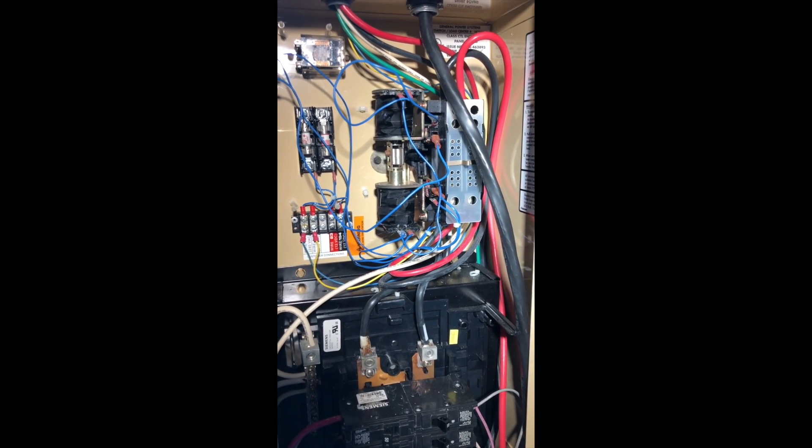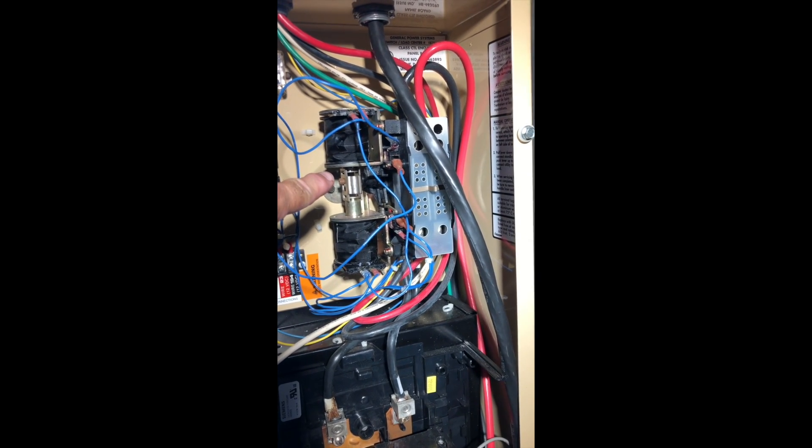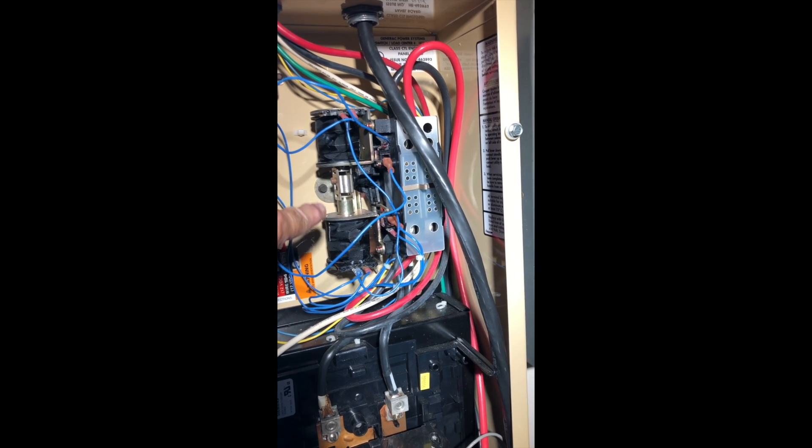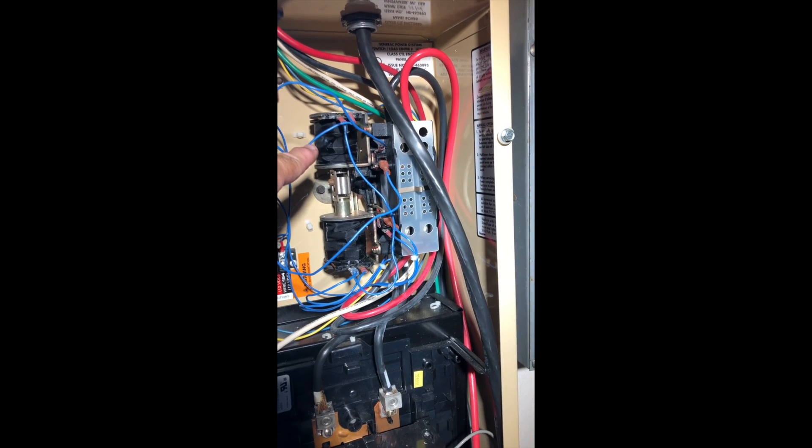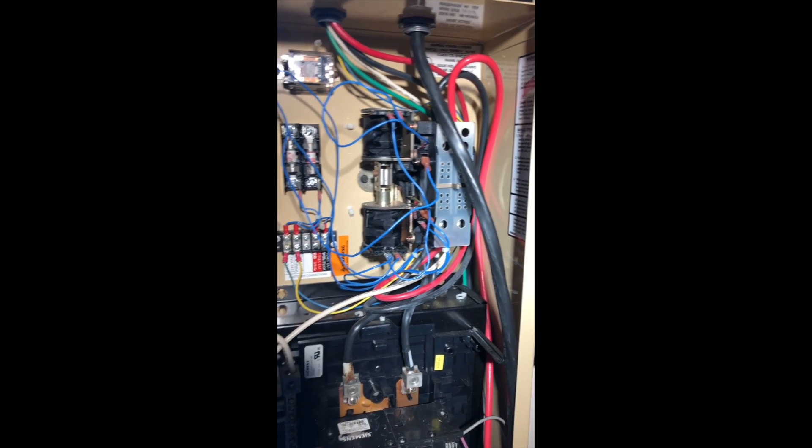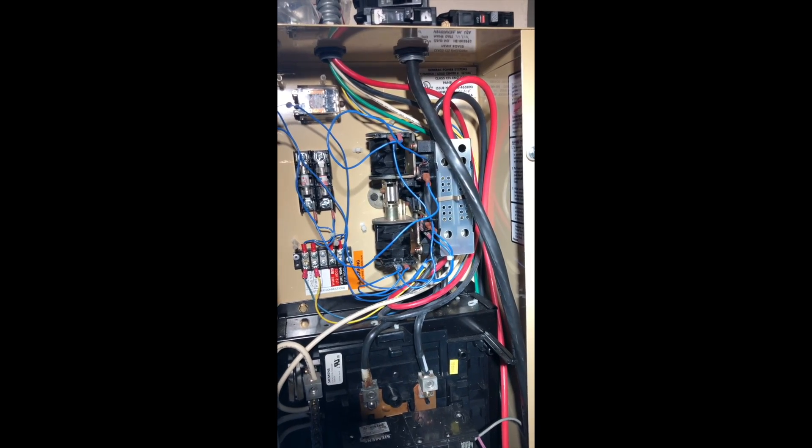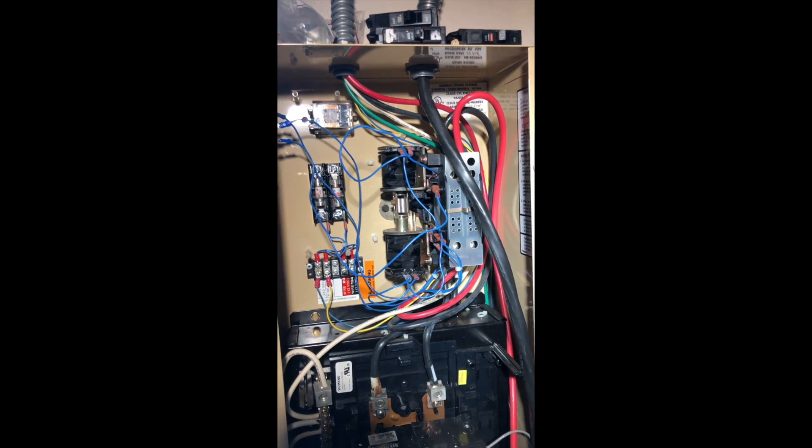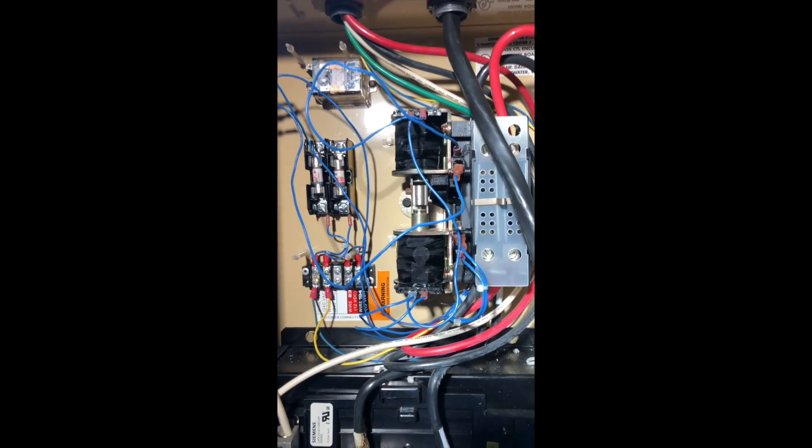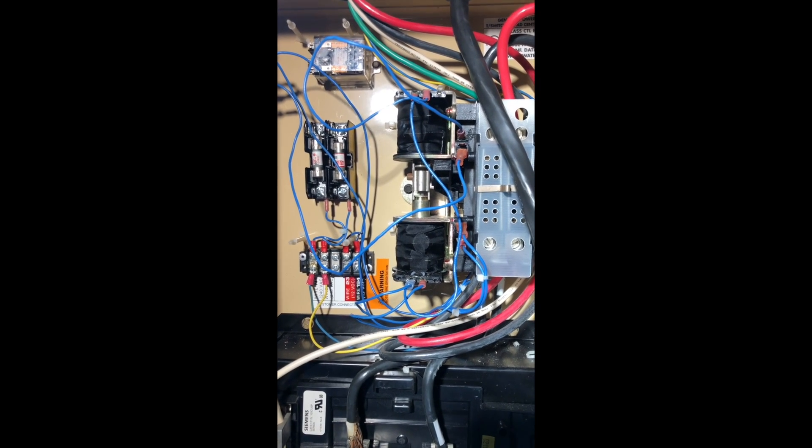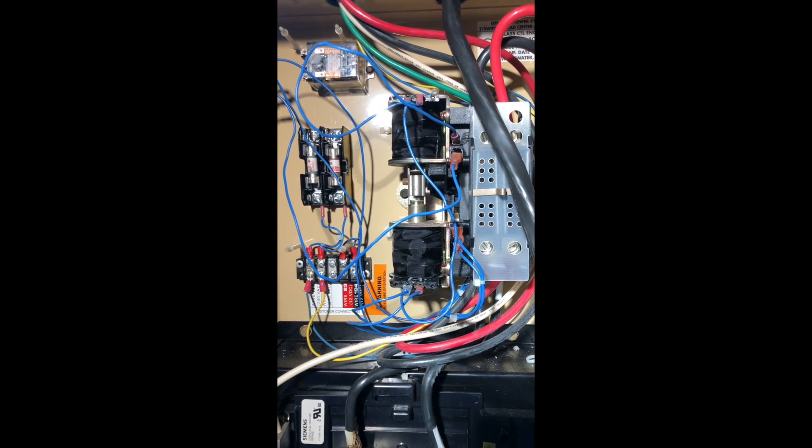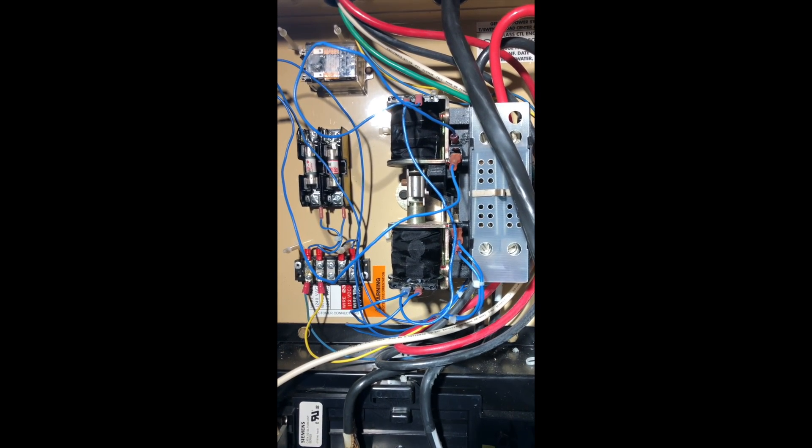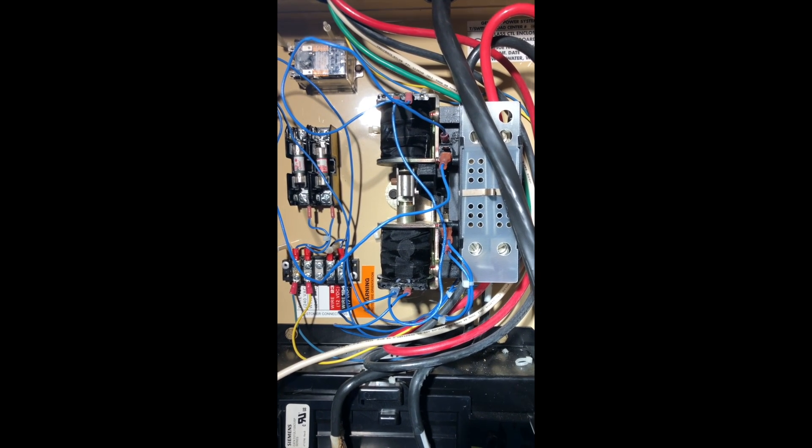I figured out how to - this is the transfer switch mechanism. Basically, it's two electromagnets, one on top of each other. They are AC powered, they're not 12 volt powered. There is a 12 volt component to this that has to do with the sensing unit that sends the commands to the generator to start, and also when to switch the power over from mains to the generator.